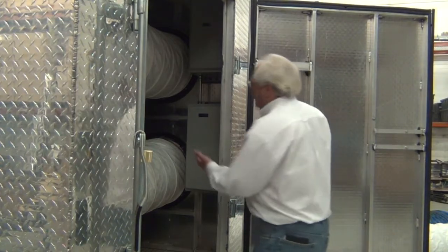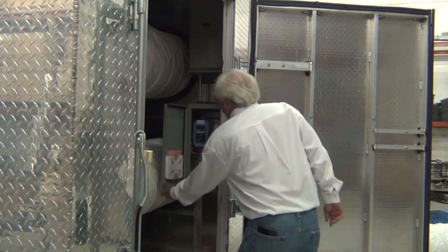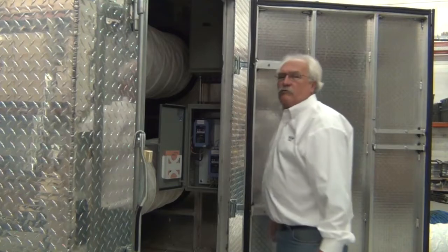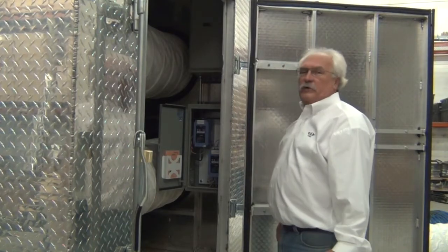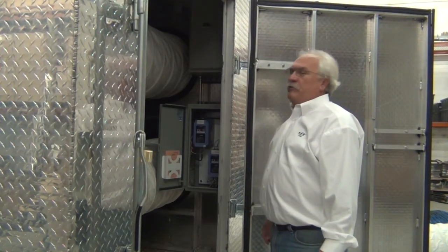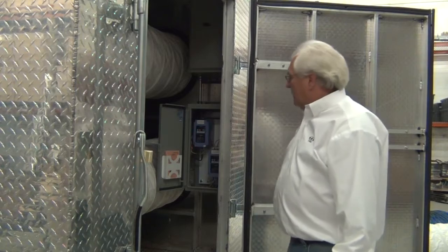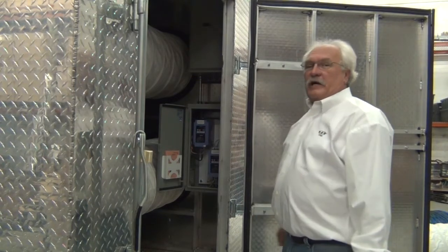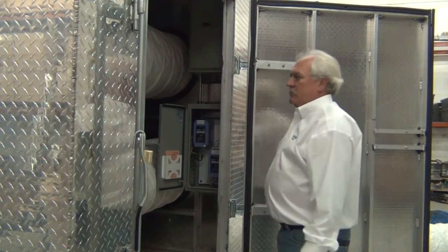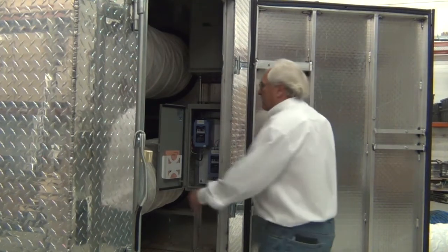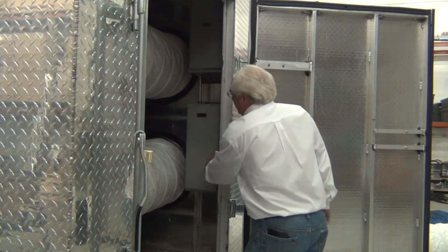In the blower compartment toward the rear of the unit, we've mounted the 4 variable frequency drives for the individual blowers to control the RPM and the amperage draw of the units on startup. These units are housed back here and would typically not require much service, if any, so they're provided in a ventilated cabinet in the clean airspace.